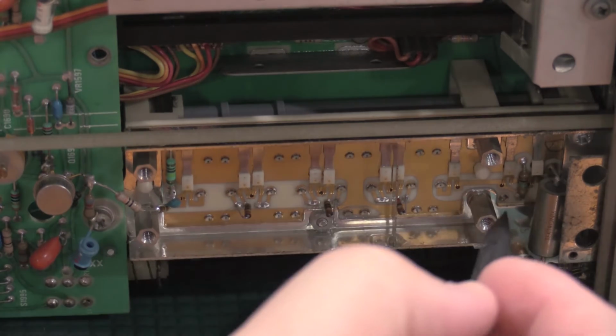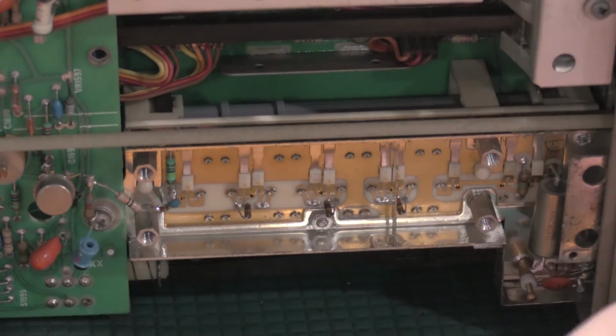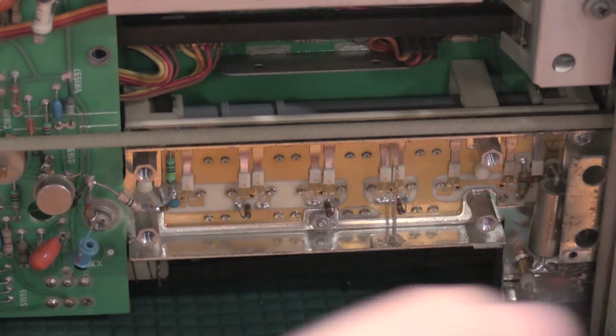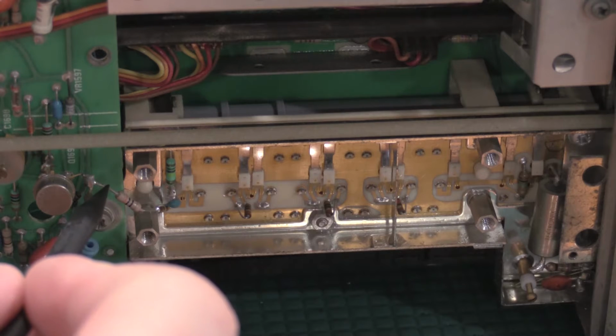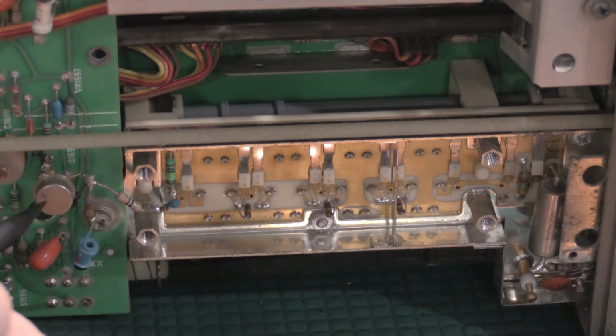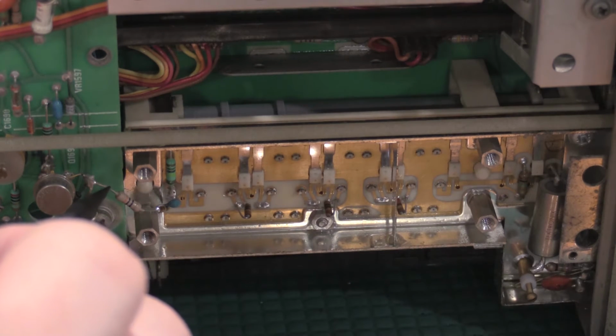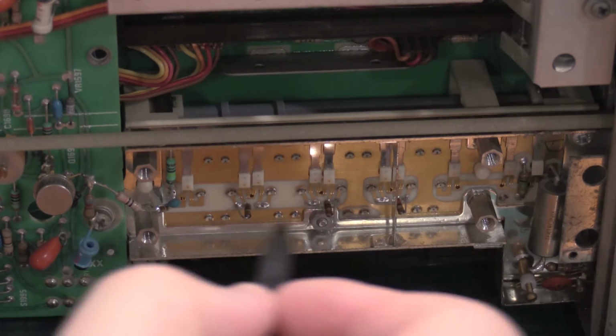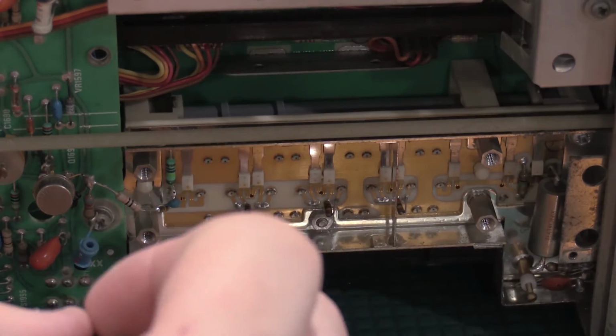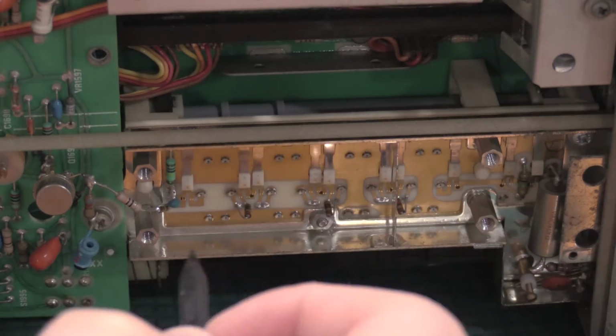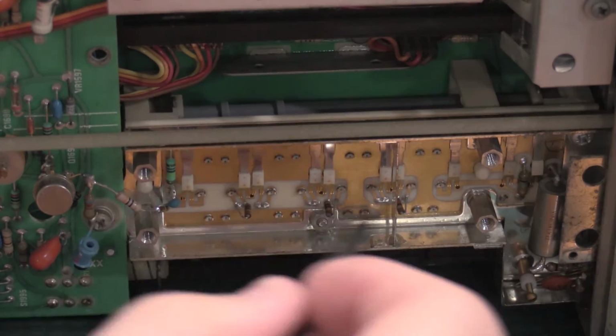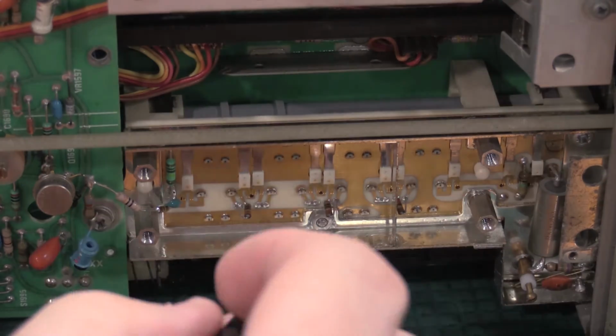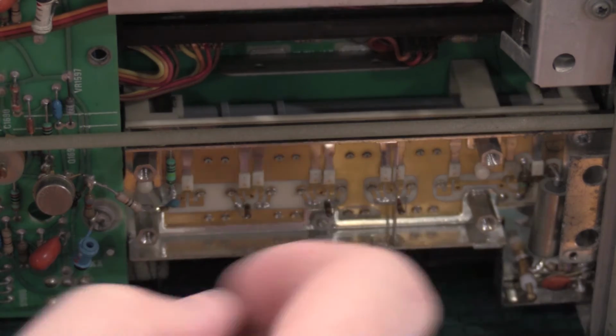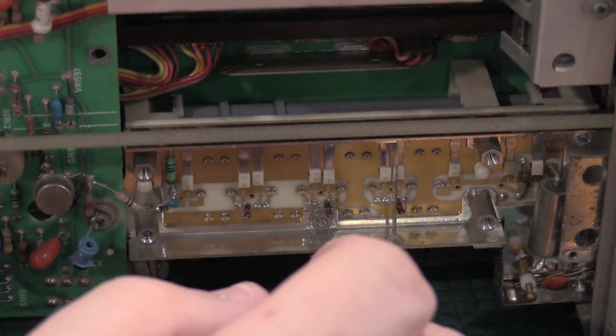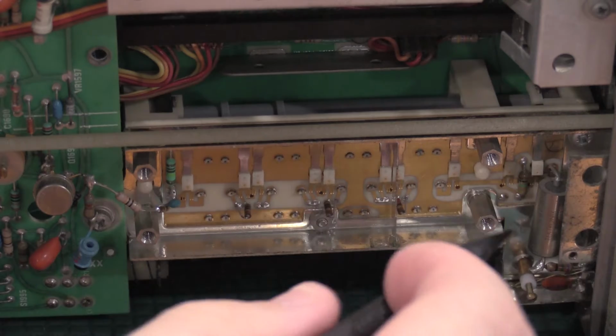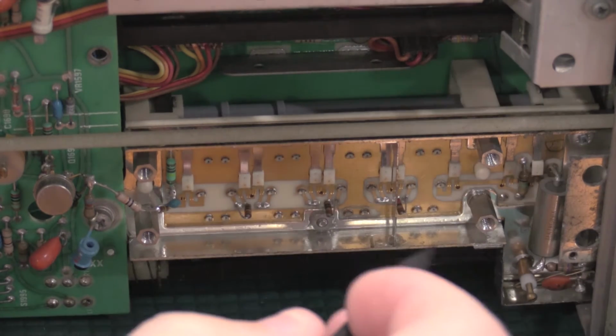So the way you can check an attenuator is, you don't even need the scope. If you feed the signal in, if you pick up the signal right here, right before it hits this FET, then if you have signal here, the attenuator block is working. If you don't have signal here, it's getting lost in here. Usually it's these switches. With all the Tek stuff that I've repaired and refurbished recently, I have not run into a bad attenuator. I have not run into a blown out attenuator.